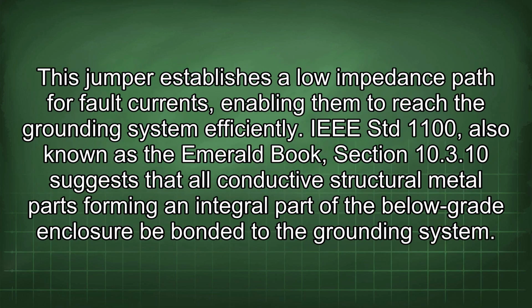This jumper establishes a low impedance path for fault currents, enabling them to reach the grounding system efficiently. IEEE Std 1100, also known as the Emerald Book, Section 10.3.10 suggests that all conductive structural metal parts forming an integral part of the below-grade enclosure be bonded to the grounding system.